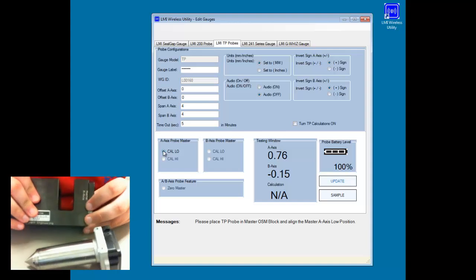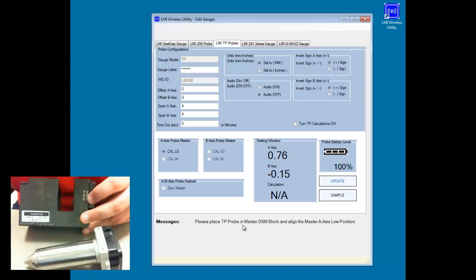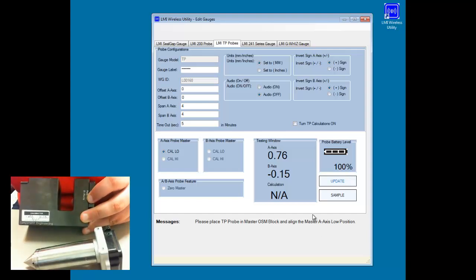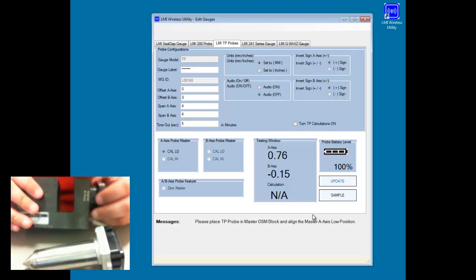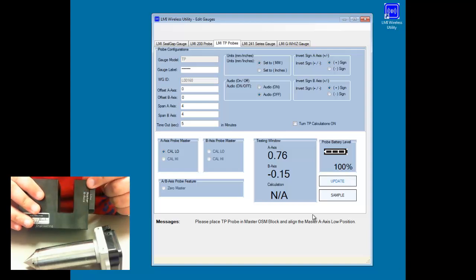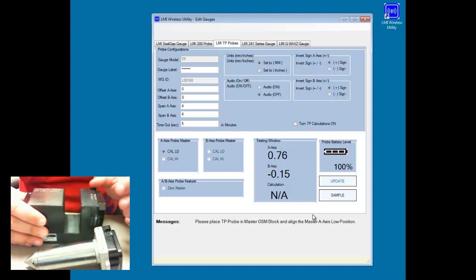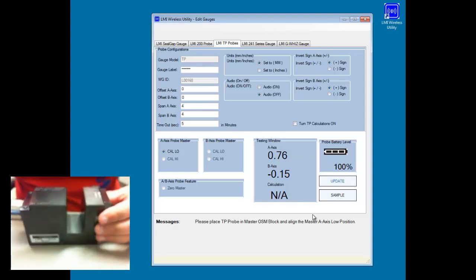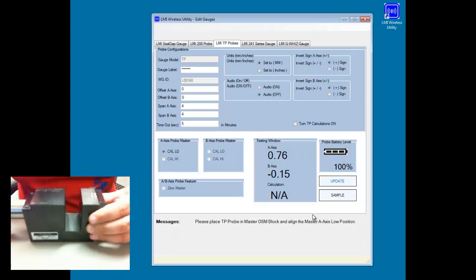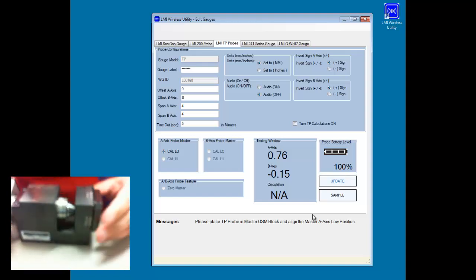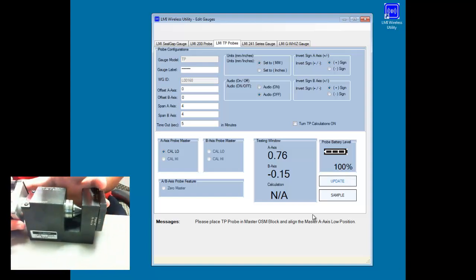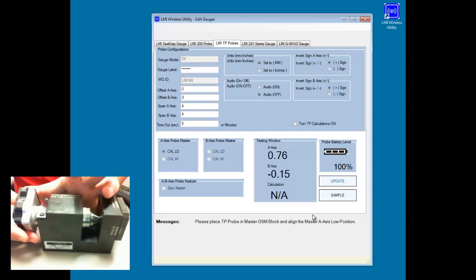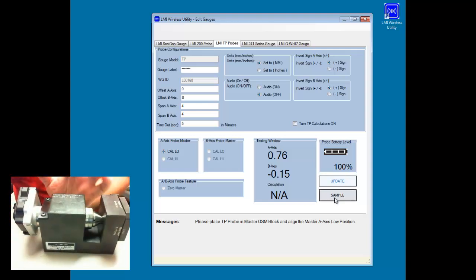I want to make sure that I'm placing the TP probe in the master OSM block and aligning the master A axis in the low position. So I'll pull out the end pin here and rotate it to where I have low in the master A axis position here. I will then insert the probe. And I'm going to push this all the way back in here to make sure that it's a tight fit. And then I'll click on the sample button.